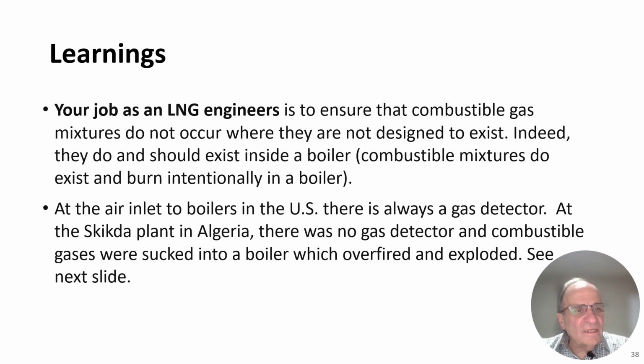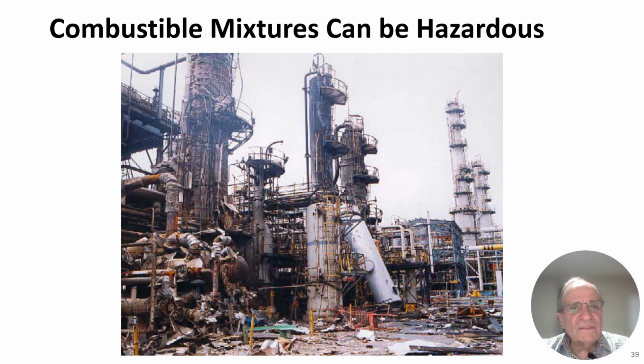The learning from this is that your job as LNG engineers is to ensure that combustible gas mixtures do not occur where they are not designed to exist. Indeed, they do and should exist inside a boiler. Combustible mixtures do exist and burn intentionally in a boiler. At the air inlet to boilers, in the US, there's always a gas detector that's required by code. At the Skikda plant in Algeria, there was no gas detector and combustible gases were sucked into the boiler, which overfired the boiler and caused the boiler to explode. See the next slide. As can be seen, the results of the Skikda incident were catastrophic, at least in this part of the plant.